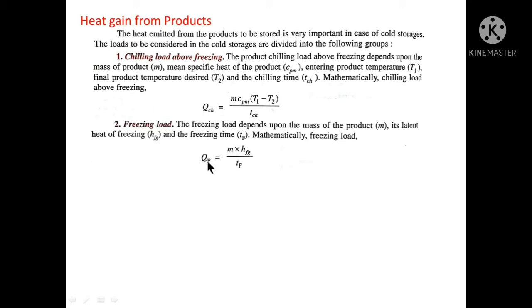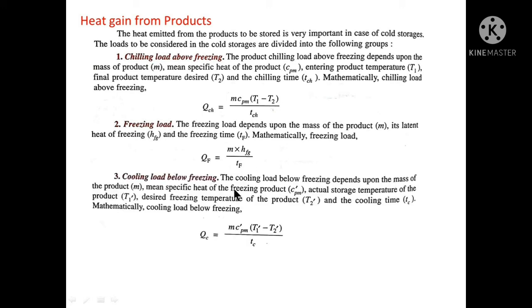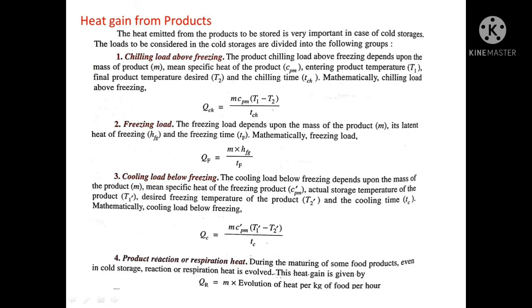Next is the freezing load, given by QF = M·HFG / TF. Next is the cooling load below freezing, given by QC = M·C'PM·(T1' − T2') / tC. Next is the product reaction or respiration heat — during the maturing of some food products, even in cold storage, reaction or respiration heat is evolved. This heat gain is given by QR = M × heat evolution per kg of food per hour.